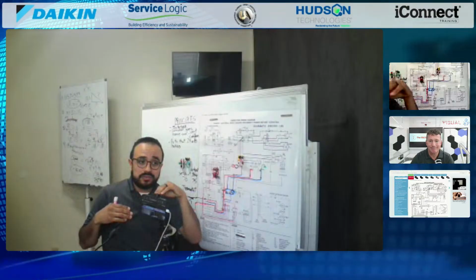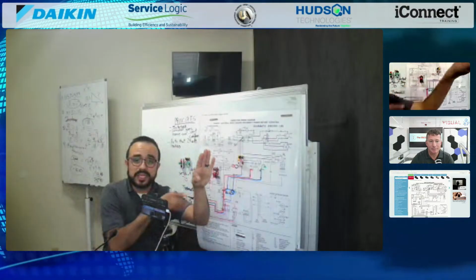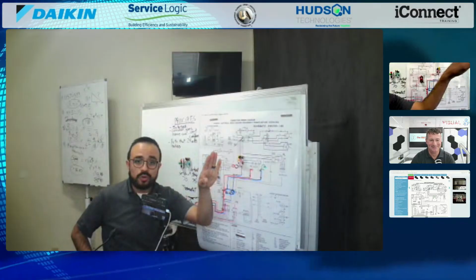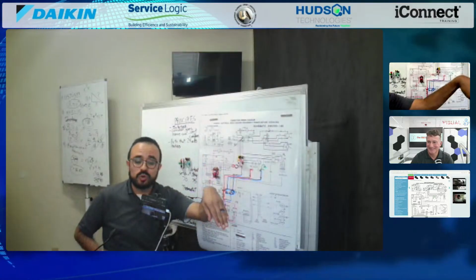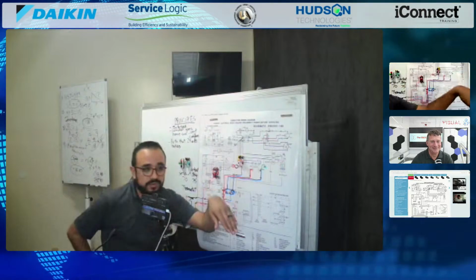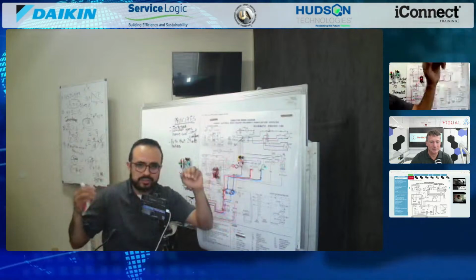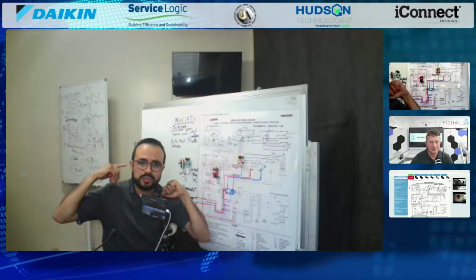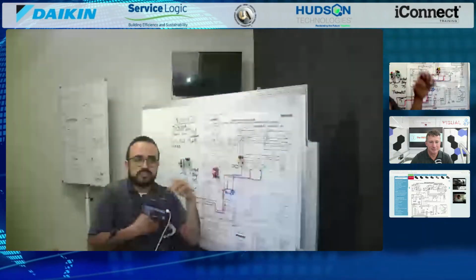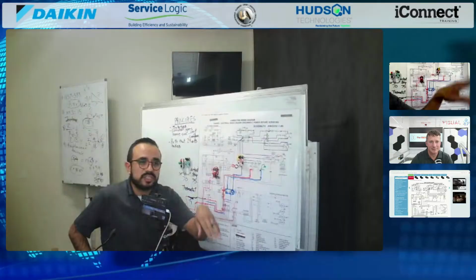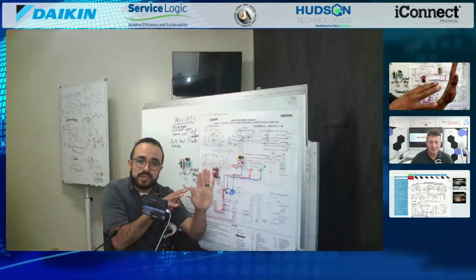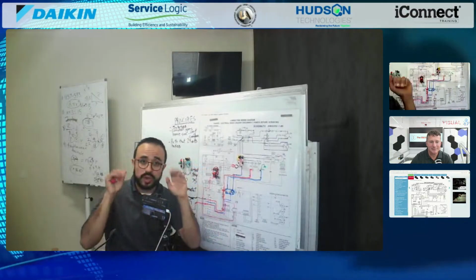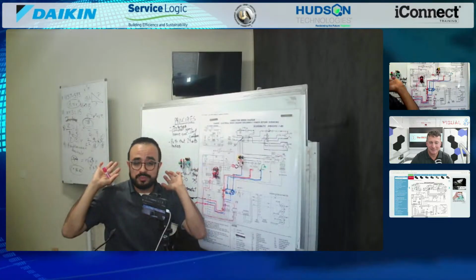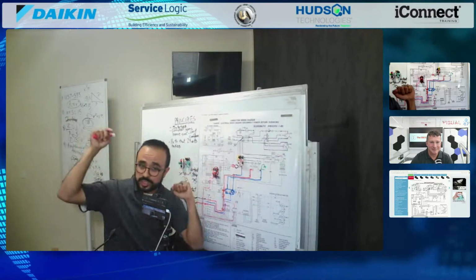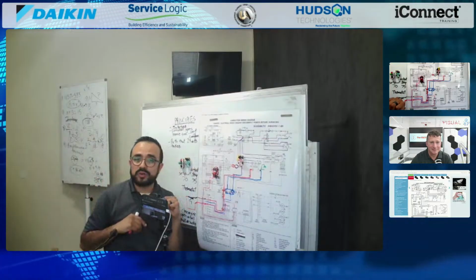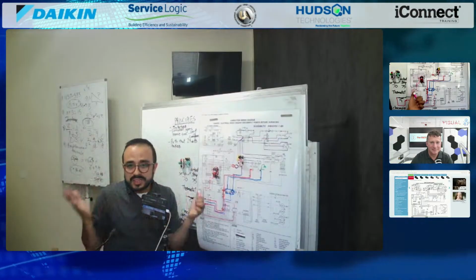So if that bridge is open, Mario can't go through because the pressure's too high. Or if it's low on refrigerant, the pressure's too low, Mario can't go through. If there's a freezestat reading the temperature outside and it's too cold, the bridge is going to stay open because it's doing its job. So safety is just to alert you, hey, Mario's not going through because we have an issue. And once the issue gets fixed, then Mario can go through, but not right now. So that's kind of the concept.